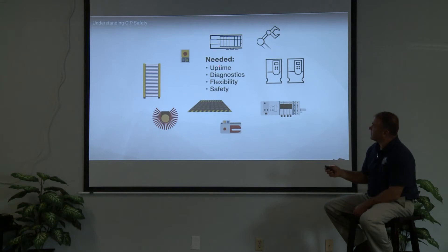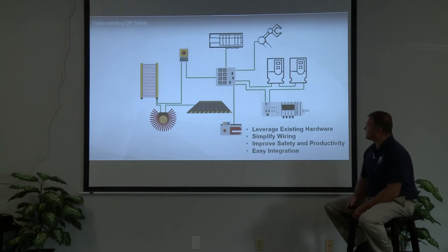What we need is uptime, diagnostics, flexibility, and we've got to keep everything safe. So what CIP Safety does — and if anyone doesn't know, CIP Safety is actually a Common Industrial Protocol which uses Ethernet IP. As you can see, we have light curtains, safety mats, scanners, a multi-axis box, drives, the PLC, e-stops, and push buttons. When we integrate CIP Safety, we can run all this back to a switch and then take it back to a PLC, as long as that is a safety processor.